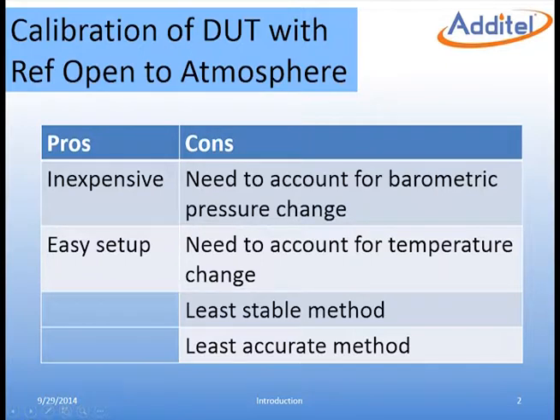However, this method has some considerable disadvantages. First, because the low or reference ports are open to atmosphere, the change in barometric pressure needs to be accounted for. Depending on the calibration environment, this error can be significant. The influence of temperature effects also presents a challenge with this method. This is the least accurate method of calibration.